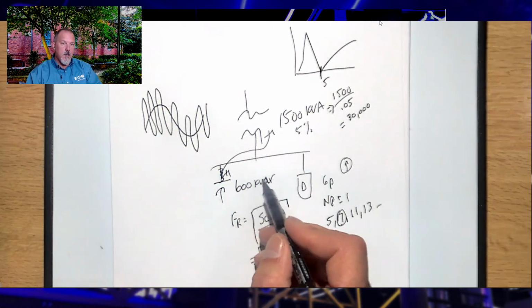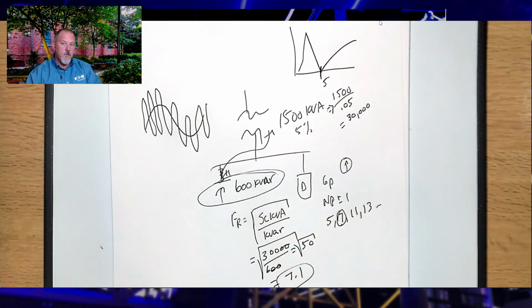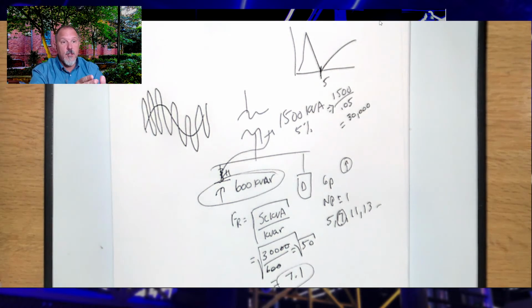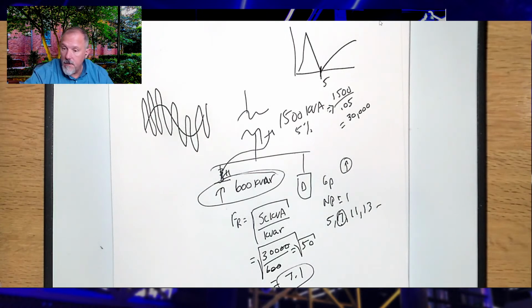And remember what I said: if it's a harmonic filter, at 60 hertz it still looks like a capacitor. It still does its power factor job. But you don't have to worry about that. So that's called tuning the system, right? Tuning the filter, yeah. So you're basically setting that point for the lowest harmonic that you'll see. So your series resonance is much lower, and you're never going to see it. And that's basically an analysis that somebody will have to do. Unfortunately, just placing power factor correction caps in a system is not that simple. You should do this analysis.